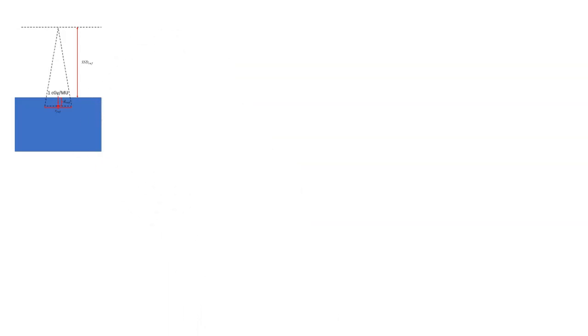Here is the reference condition shown on the top left. We know that the accelerator is giving one centigray per MU at this point at whatever your calibration distance, field size, and SSD is.